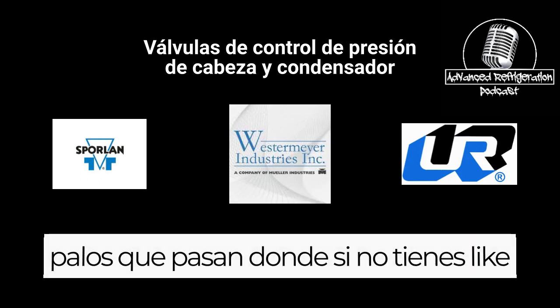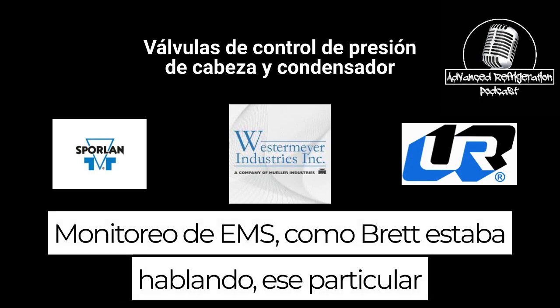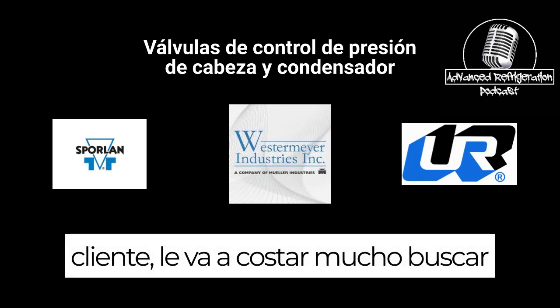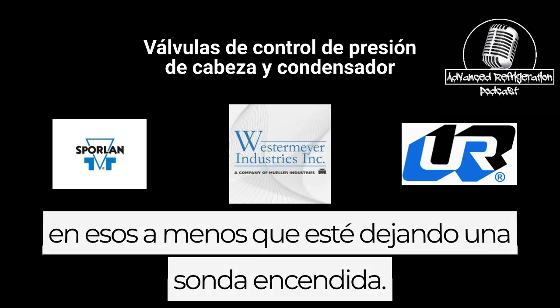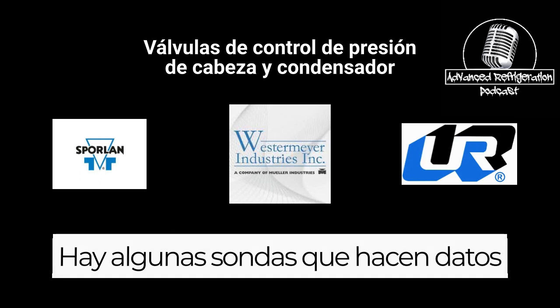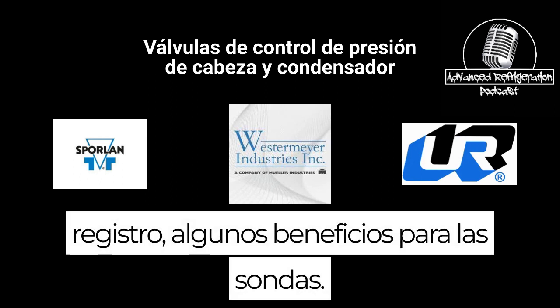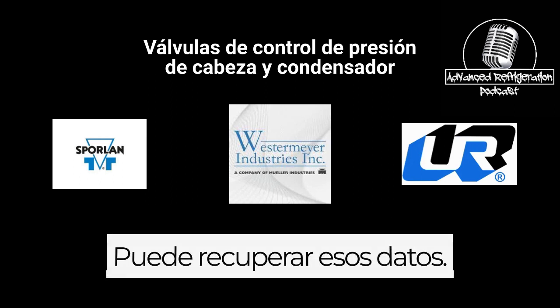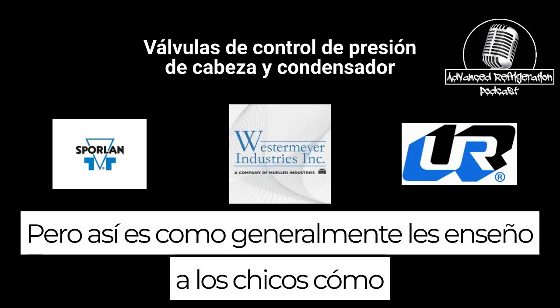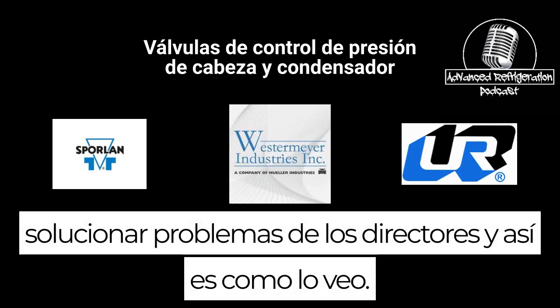besides the random sticks that happen, where if you don't have EMS monitoring, like Brett was talking about with that particular customer, you're going to have a hard time looking at those unless you're leaving a probe on there. Some probes do data logging, which is a benefit, since you can pull that data back. But that's how I generally teach guys how to troubleshoot headmasters, and that's how I look at it.